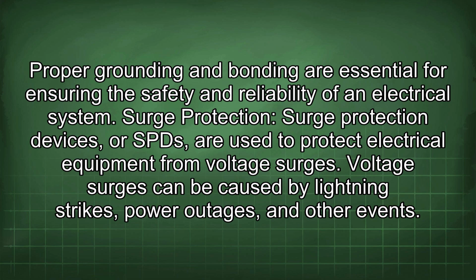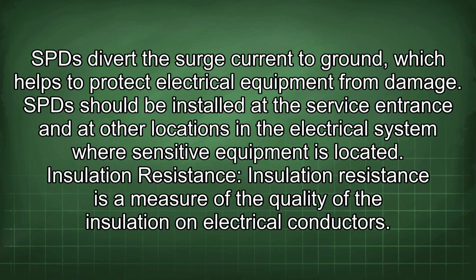Surge protection. Surge protection devices, or SPDs, are used to protect electrical equipment from voltage surges. Voltage surges can be caused by lightning strikes, power outages, and other events. SPDs divert the surge current to ground, which helps to protect electrical equipment from damage. SPDs should be installed at the service entrance and other locations in the electrical system where sensitive equipment is located.